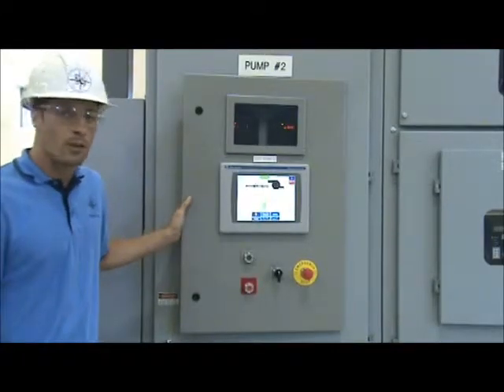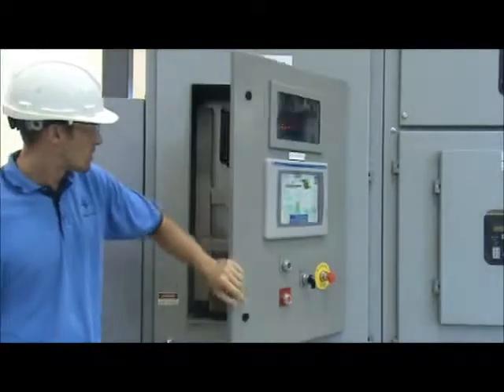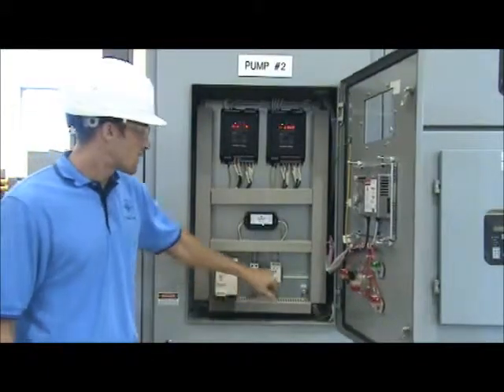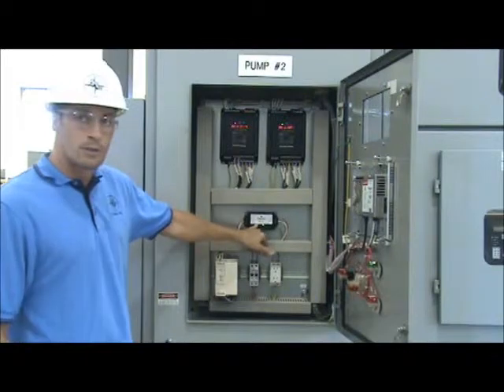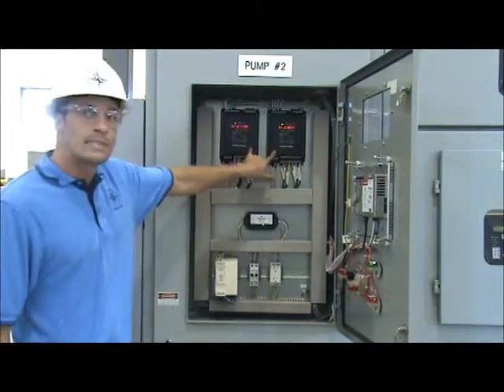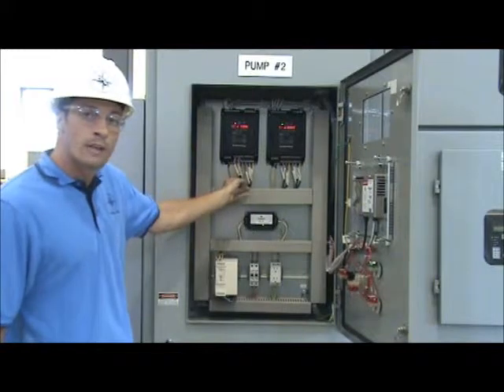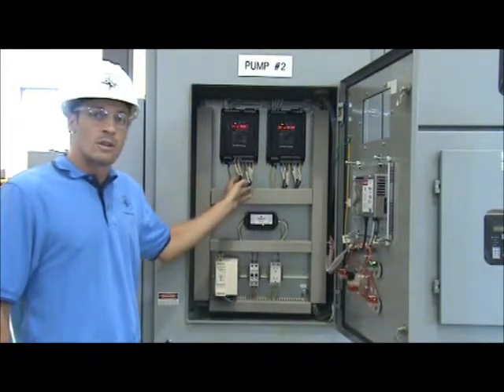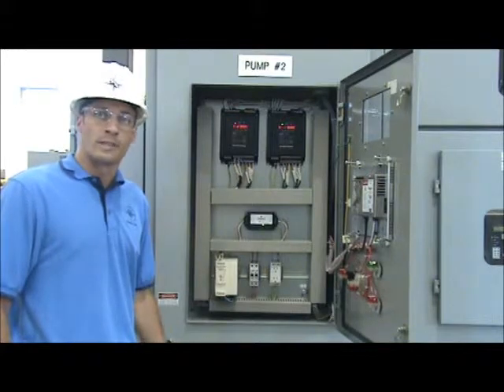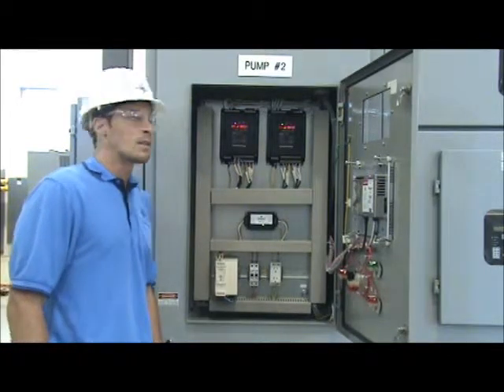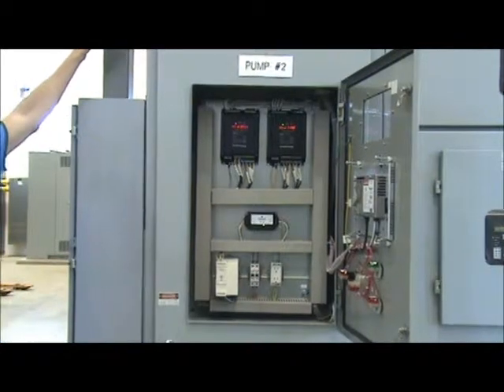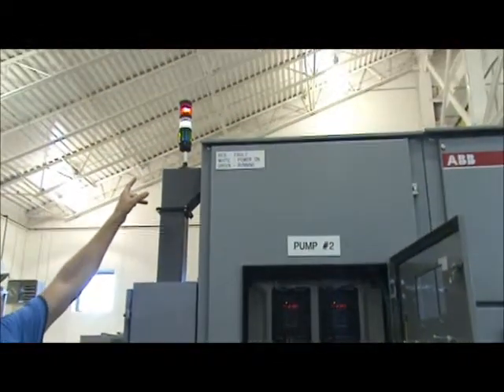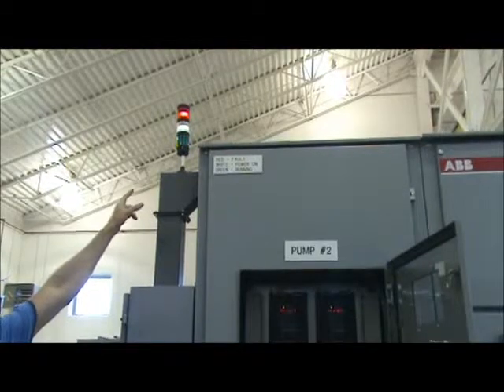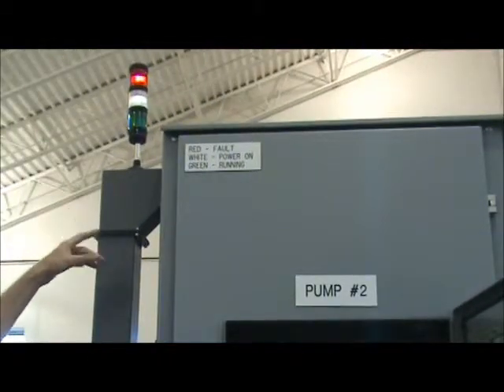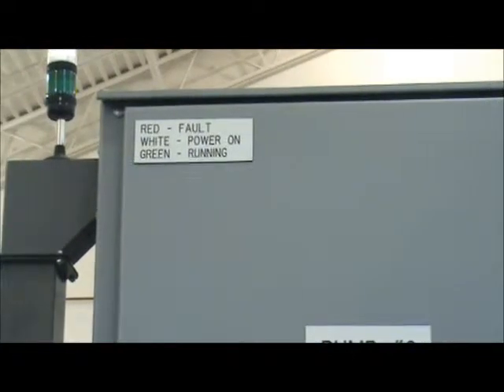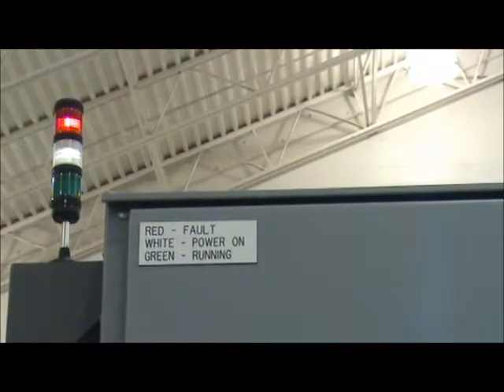The center low voltage compartment contains the HMI, our DC power supply, a convenience outlet, a line filter with surge protection, and then the RTD boards, which the RTDs are directly wired into, which eliminates a terminal board, which would provide cold junction points, which may screw up the signal. Then also, we have our stack light. White shows that power is on to the unit, or medium voltage. Green shows the pump's running, and the red shows that we're in a warning or a faulted state with the controller.